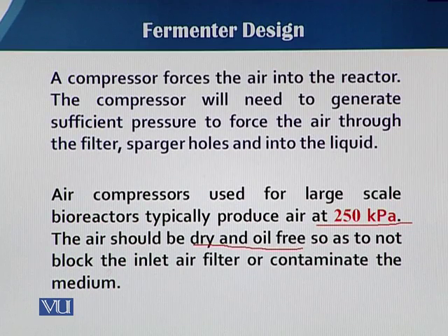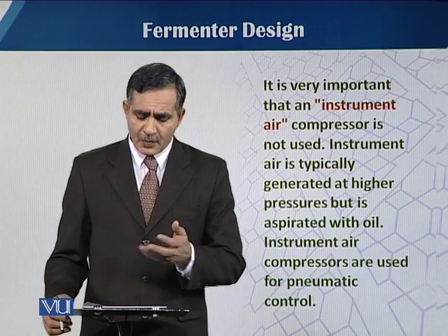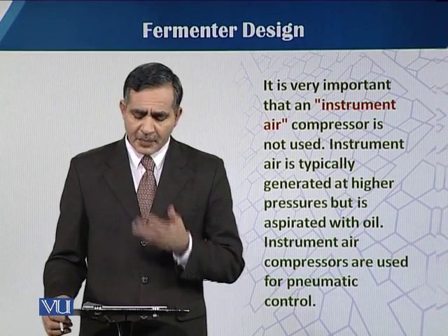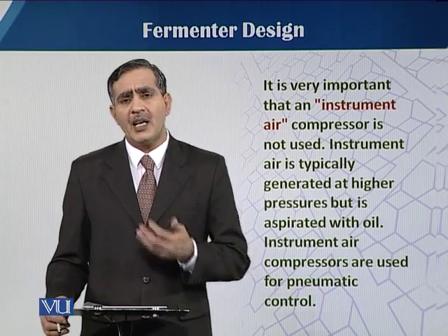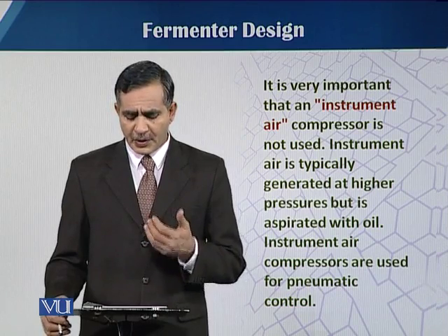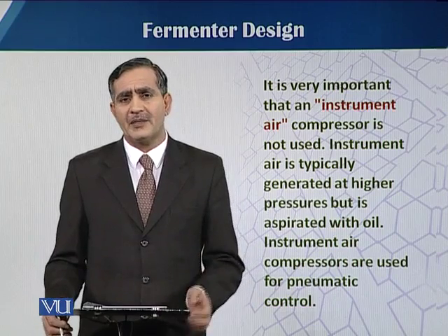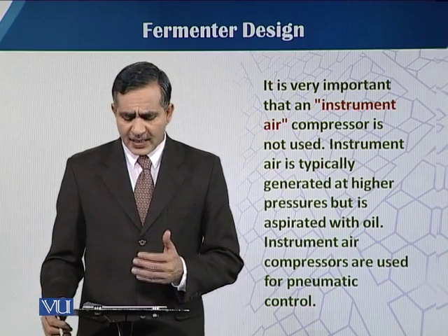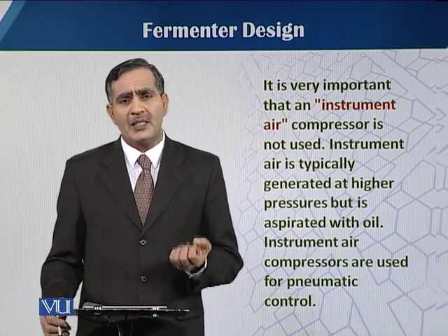So while selecting the compressor for fermentation needs, we have to be very careful, because, as with instrument air, a compressor of that kind is not used. Our air should be oil free, and we have to use compressors which produce oil free air with the required pressure.